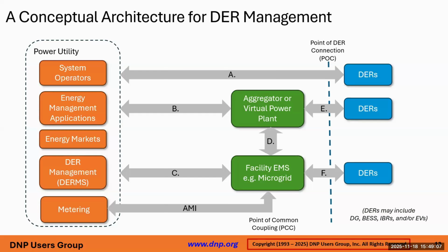For DERs that are customer-owned and providing grid services or participating in energy markets, the communication paths can look different. If DERs are aggregated by a third party, utilities typically communicate directly with the aggregator using protocols like 2030.5, DNP, OpenADR, or OCPP. The aggregator then routes the appropriate messages to individual DERs in the field using standardized or proprietary interfaces.